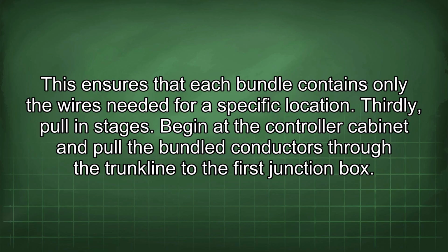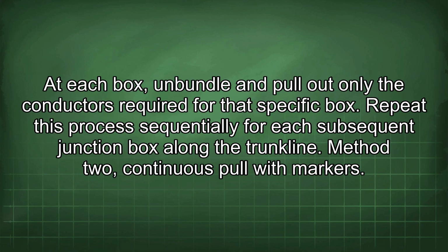Thirdly, pull in stages. Begin at the controller cabinet and pull the bundled conductors through the trunk line to the first junction box. At each box, unbundle and pull out only the conductors required for that specific box. Repeat this process sequentially for each subsequent junction box along the trunk line.